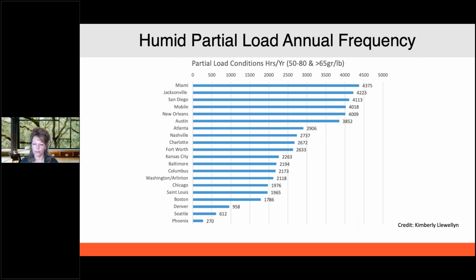A friend of mine, Kimberly Llewellyn, who works for Mitsubishi, put together this great chart on partial load conditions, where you're between about 50 and 80 degrees at higher than a 55-degree dew point, and the hours of the year that all these locations are above that. So as you can see, Miami, 4,375 hours of the year, you are at partial load conditions, all the way down to, I mean, even Phoenix. We do sell dehumidifiers, believe it or not, in Phoenix because of monsoon season, which I always find interesting.